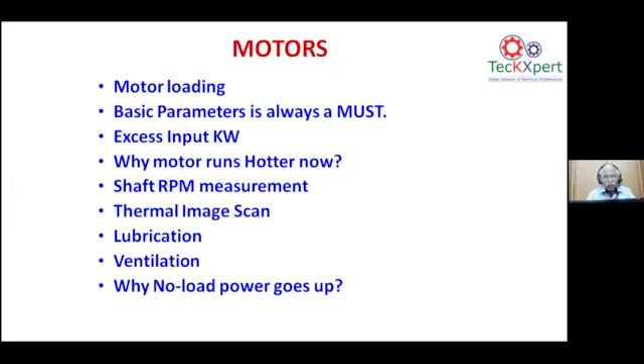So a thermal image scanner, or the infrared thermal imager, is a non-invasive tool, and it immediately gives the thermal characteristics of the given motor. Apart from the electrical characteristics, what is the input and what is the output, like the shaft RPM measurement, is also more important to us. Lubrication: we have been used to multi-purpose grease for all the motors, but specialty greasing is definitely demanded for all types of motors.